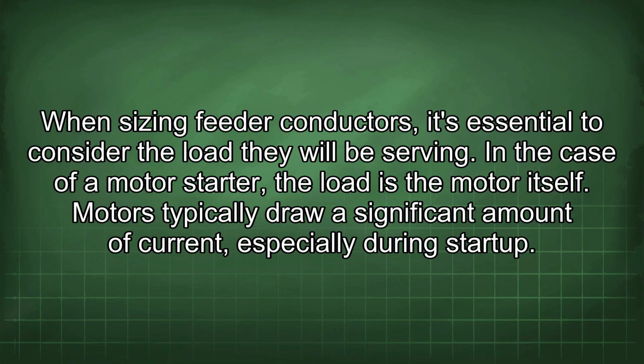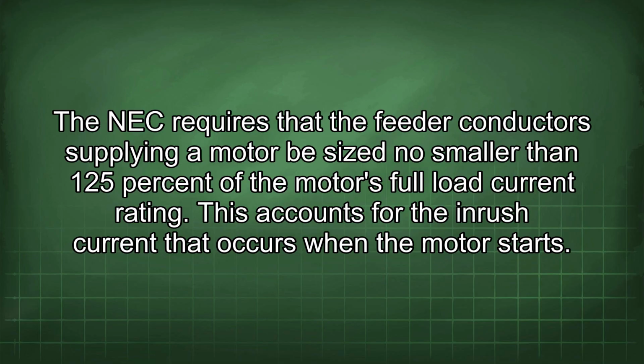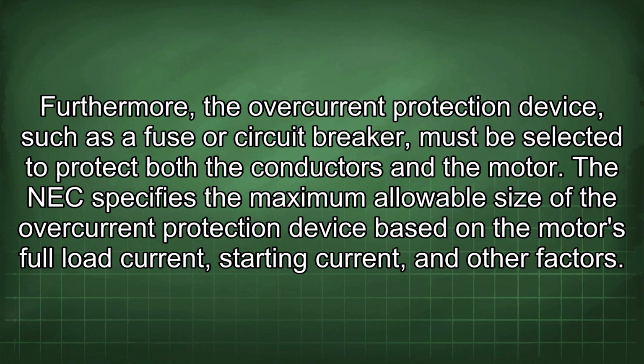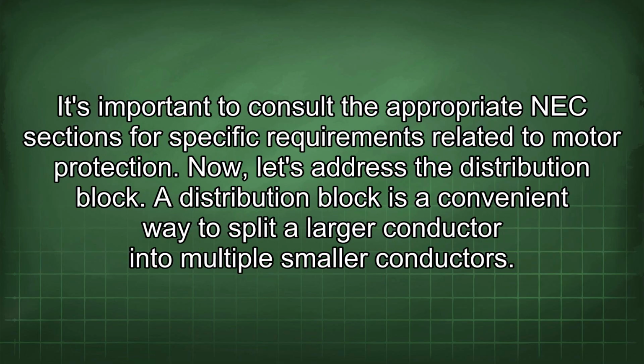In the case of a motor starter, the load is the motor itself. Motors typically draw a significant amount of current, especially during startup. The NEC requires that the feeder conductor supplying a motor be sized no smaller than 125% of the motor's full load current rating. This accounts for the inrush current that occurs when the motor starts. Furthermore, the overcurrent protection device, such as a fuse or circuit breaker, must be selected to protect both the conductors and the motor. The NEC specifies the maximum allowable size of the overcurrent protection device based on the motor's full load current, starting current, and other factors. It's important to consult the appropriate NEC sections for specific requirements related to motor protection.